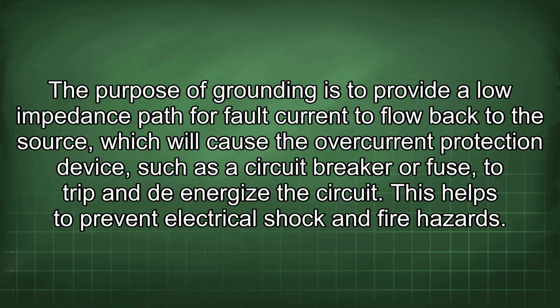The purpose of grounding is to provide a low impedance path for fault current to flow back to the source, which will cause the overcurrent protection device, such as a circuit breaker or fuse, to trip and de-energize the circuit. This helps to prevent electrical shock and fire hazards.